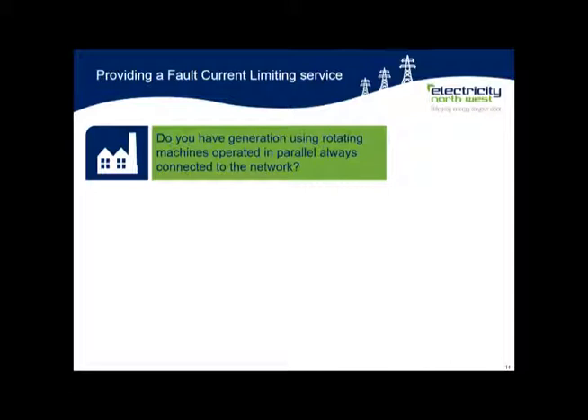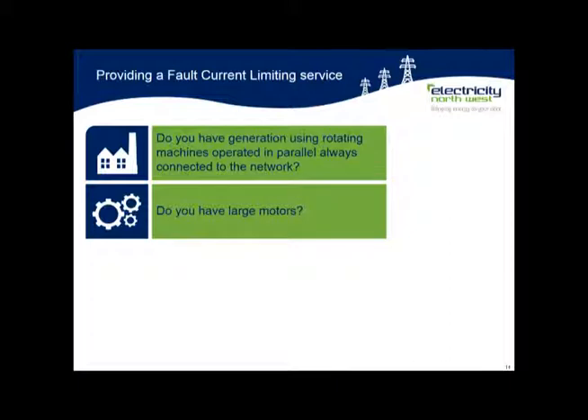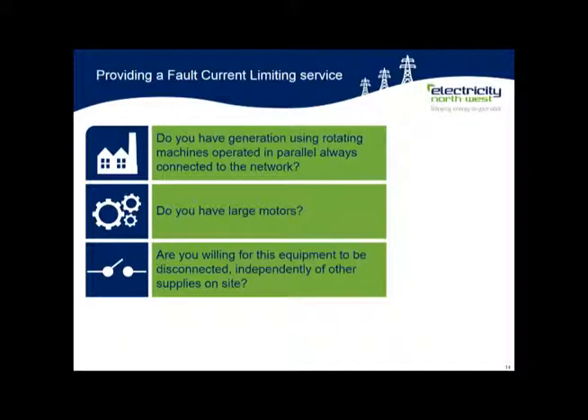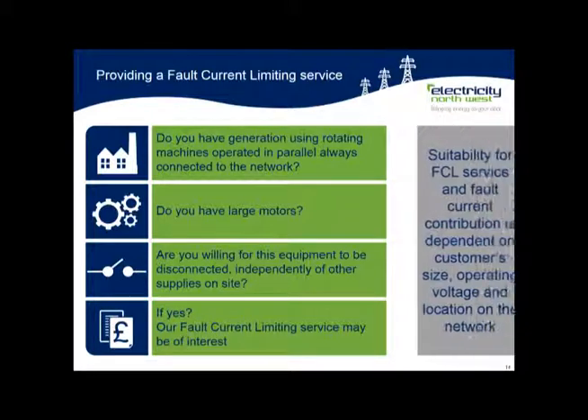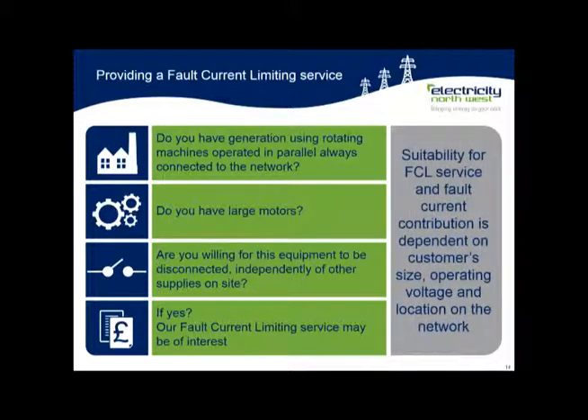So, do you have generation using rotating machines operated in parallel, which is connected to our network? Do you have large motors? Are you willing for this equipment to be disconnected independently of the other supplies on your site? If yes, then a fault current limiting service may be of interest to you. The size, operating voltage and location on the network will affect your contribution to fault current and therefore how suitable your company may be to provide a fault current limiting service.